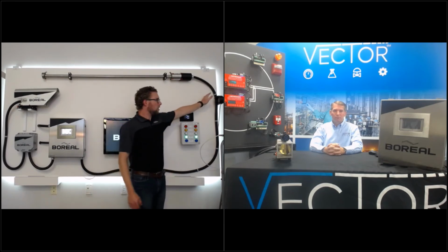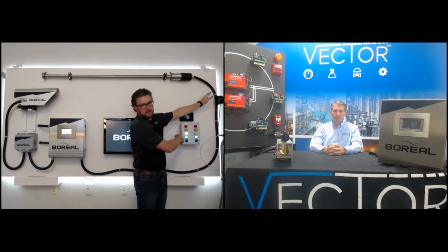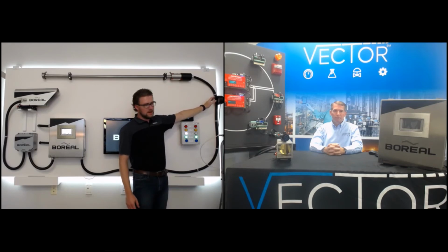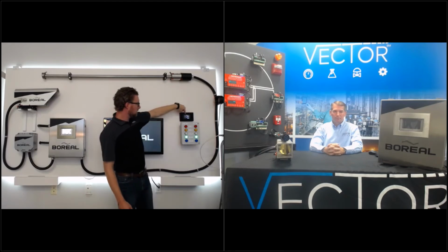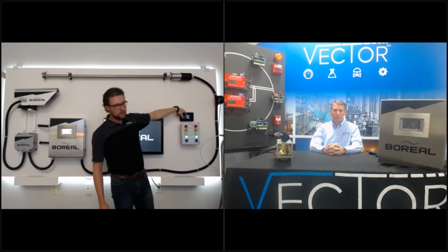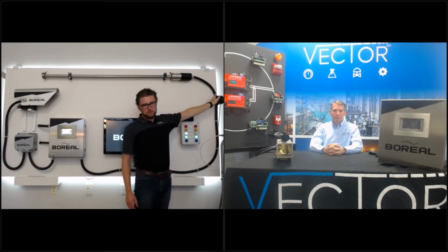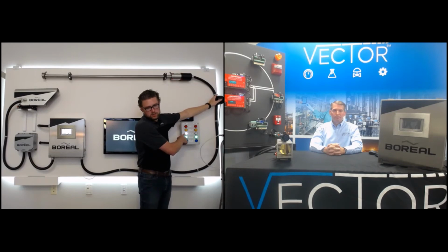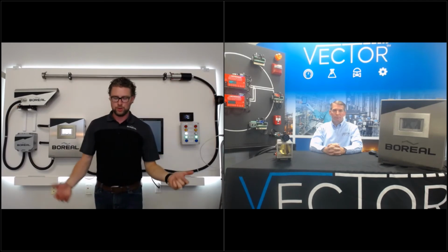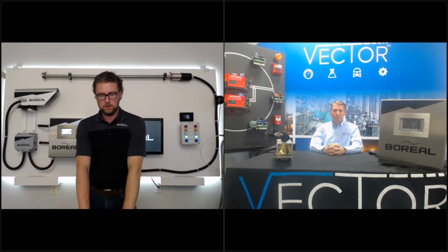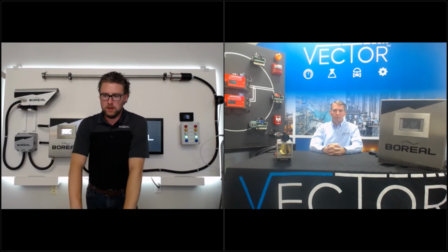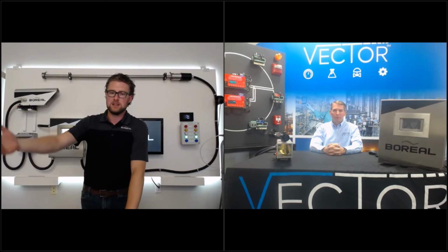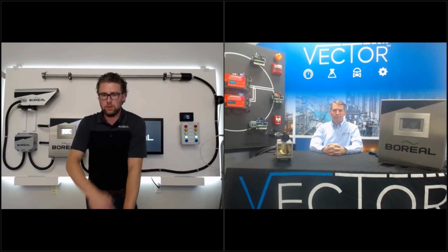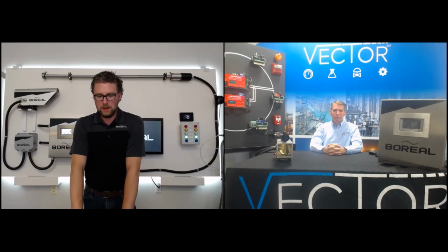And once again, if you block the beam, there is a specific fault code that is displayed and generated. You can't see here, but I have a milliamp readout. When the beam is blocked and the status condition is enabled, the analog loop goes to 2.7 milliamps to notify you that there's a specific inhibition or status condition, a low light scenario, which is very much different from a fault condition as well. Anything else, Chad, on that one? Nope, I think we covered that one well.